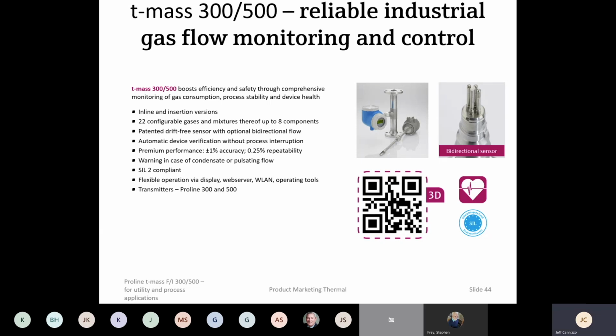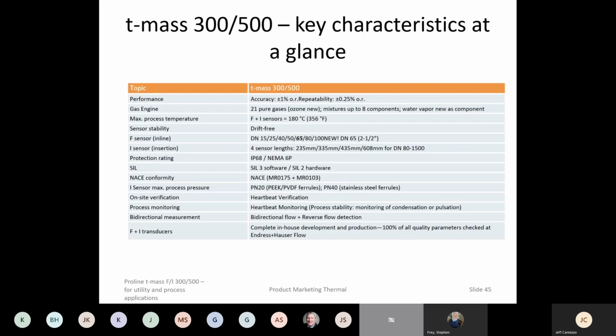And we have automatic device verification. That's part of the heartbeat technology. And it improves the accuracy of the meter overall, about plus or minus 1%, 0.25% repeatability. So if you looked at thermal mass meters, it's a meter that is within the market specifications. It's also SIL compliant, SIL 2 compliant. And all of our meters have an onboard web server for configuration. So you don't need a HART handheld. You just pretty much can plug into the meter and the onboard web server will open up. So the accuracy, again, the gas engine, 21 pure gases. You can take a look at some of those.